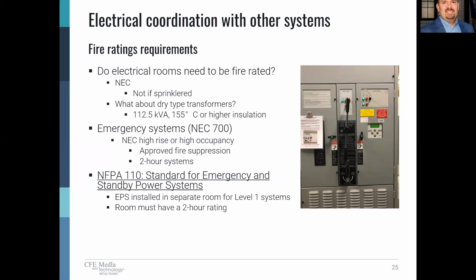Also, another instance where a rating is required is the emergency systems. This is NEC 700 systems. These need to be protected by a 2-hour rated system. This is specific to high-rise and high occupancy buildings, such as assembly occupancy. And they need to include a fire suppression system.